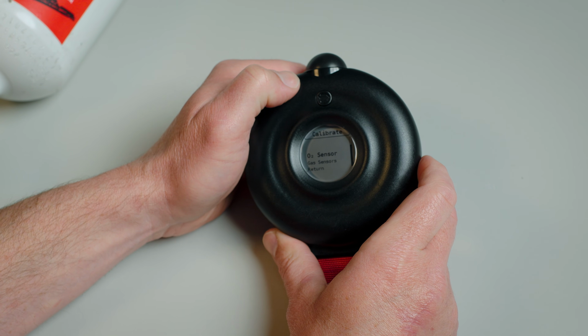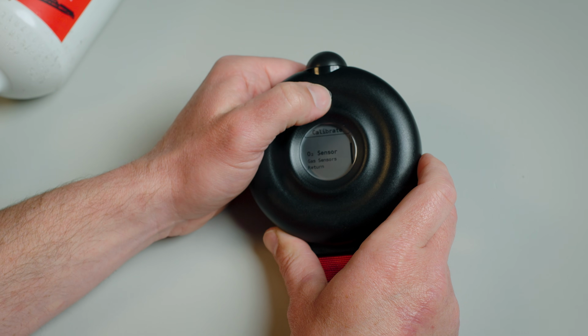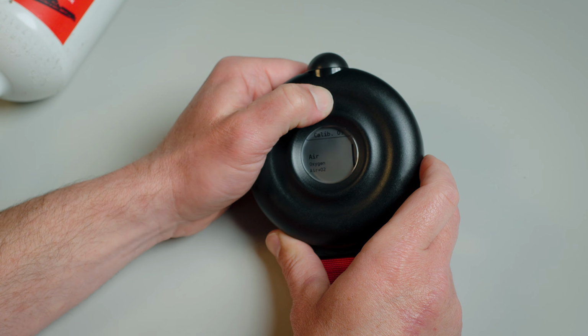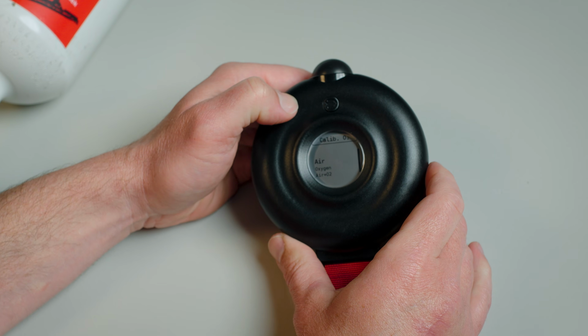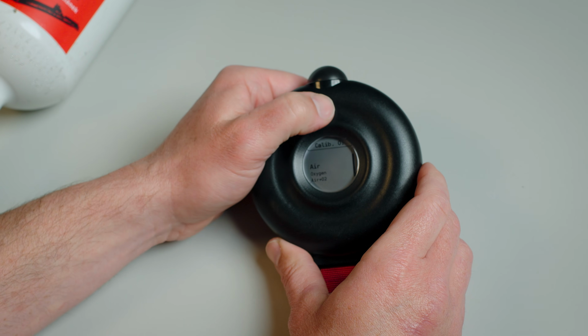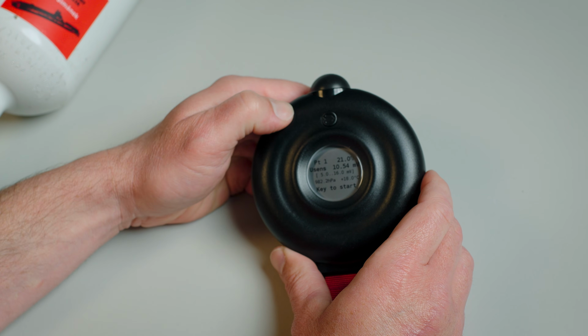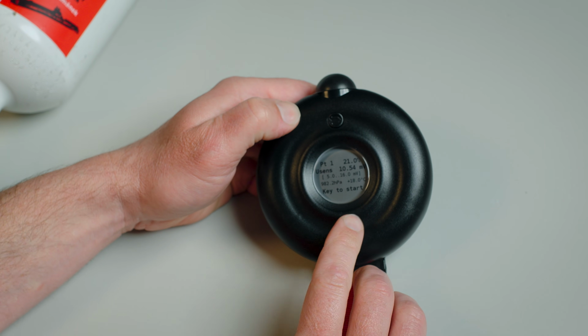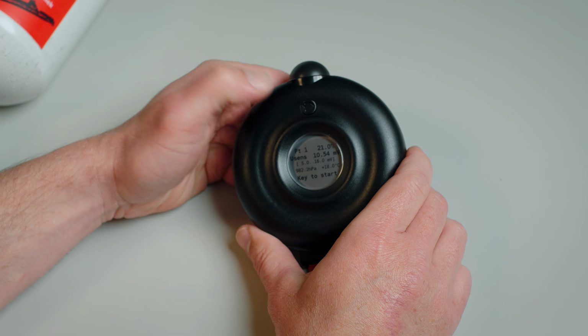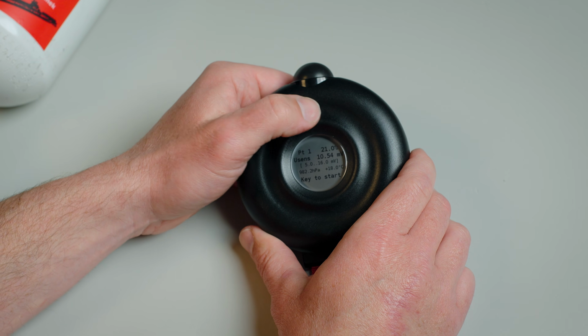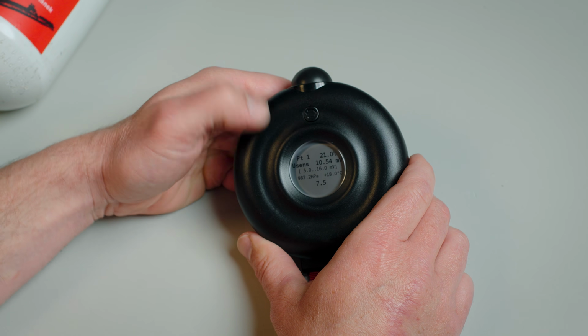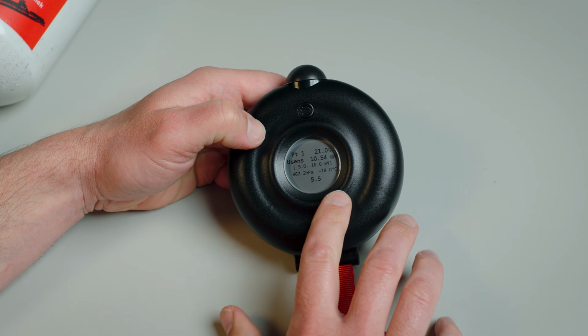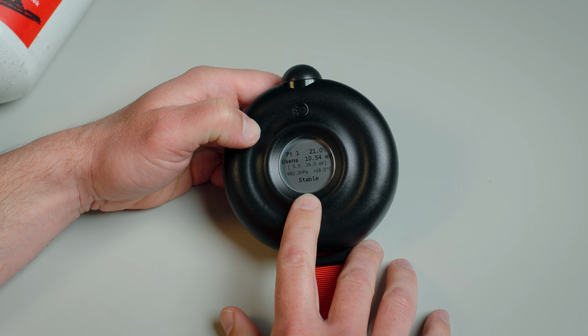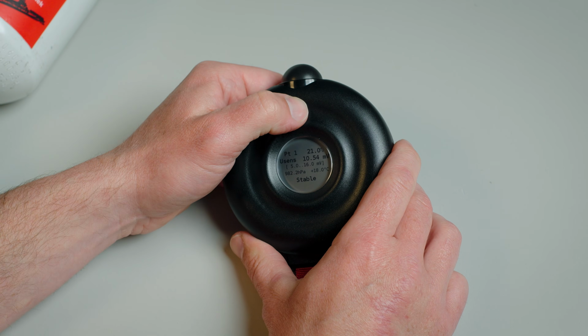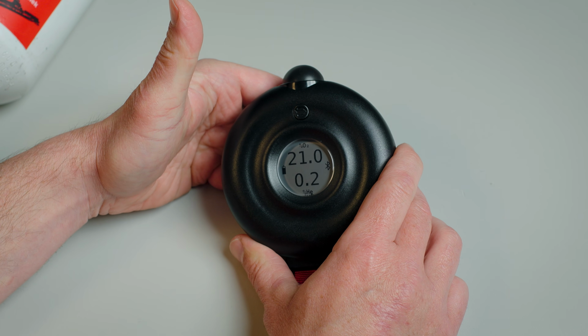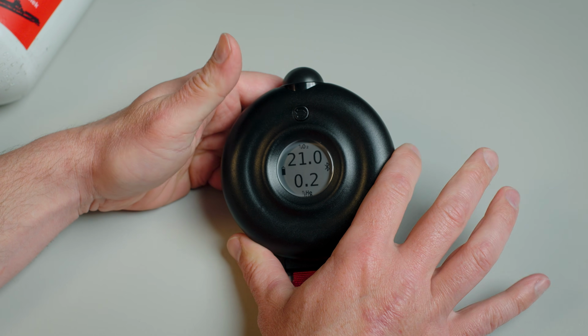We calibrate oxygen sensors, so that's the first option. And the 1-point calibration on air, which is again the first option, so long press to confirm. And now we just press a key to start the calibration. We wait for stabilization of the sensor. Now it's stable, so we just confirm the calibration with a short press and it's done.